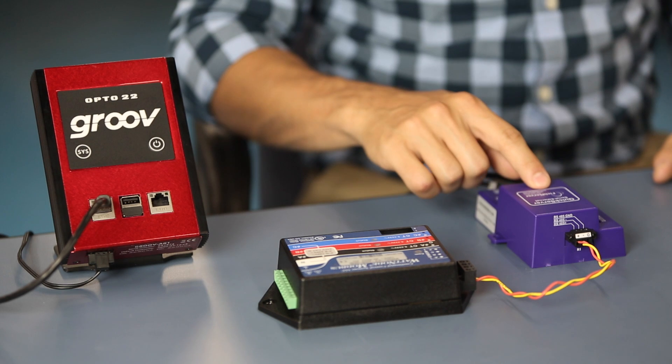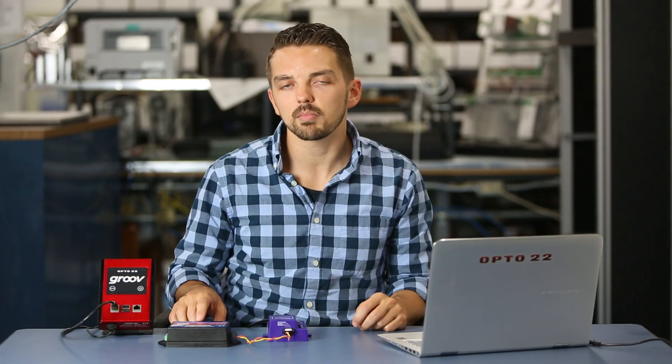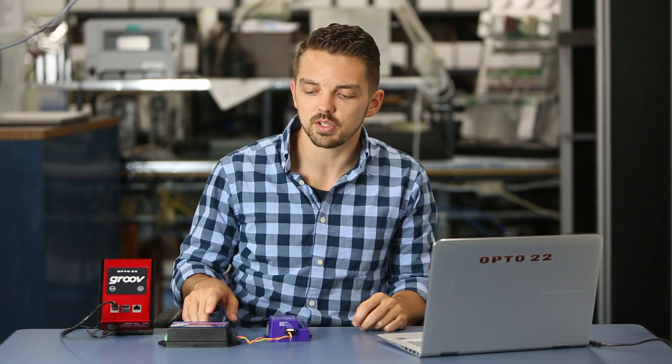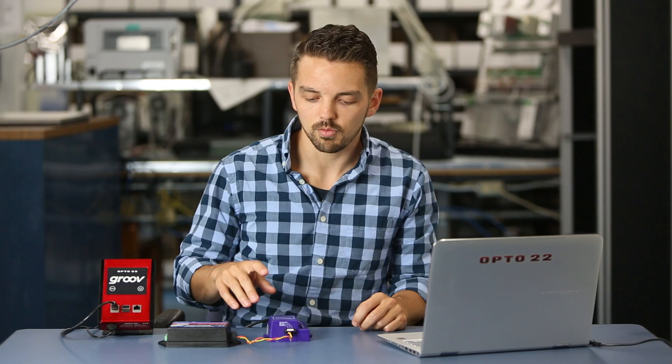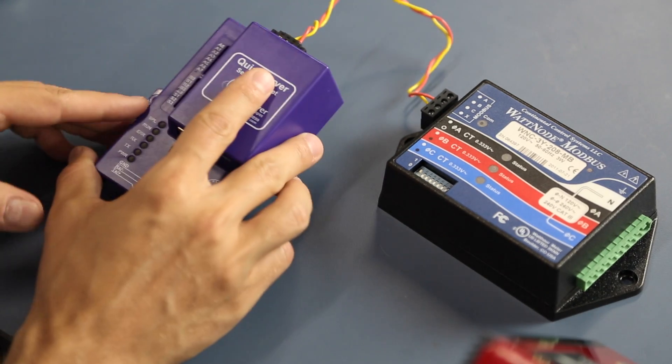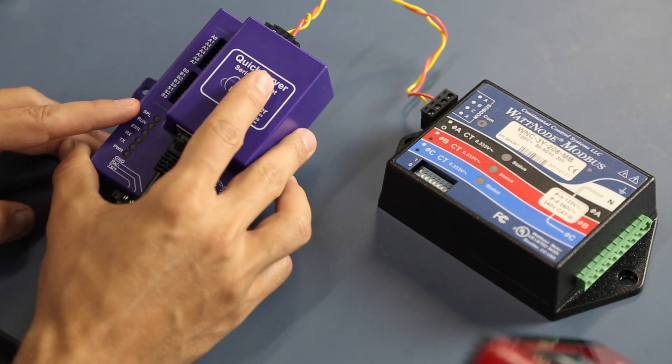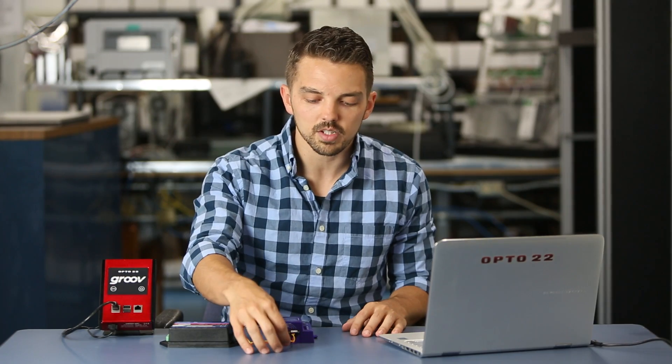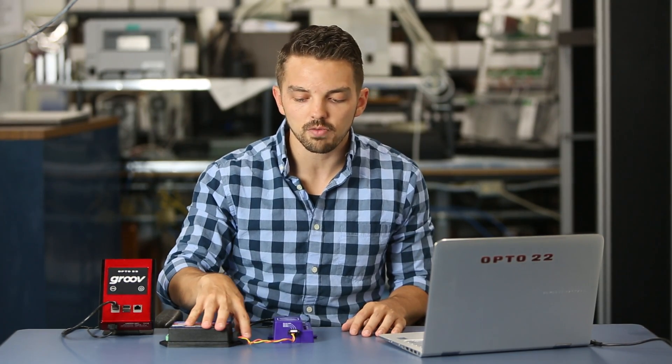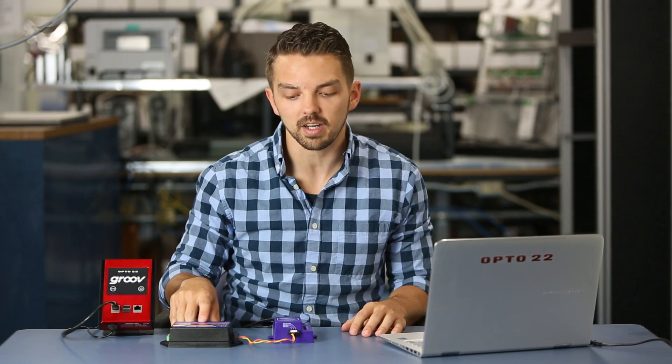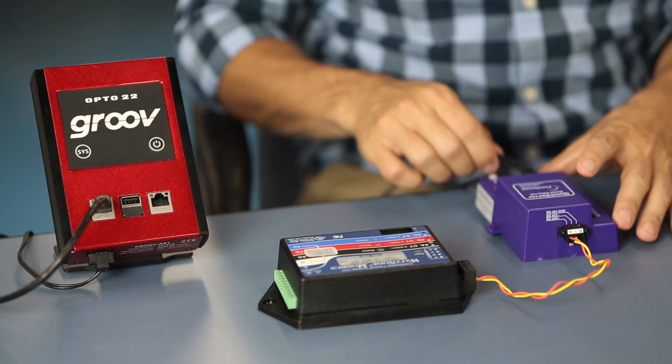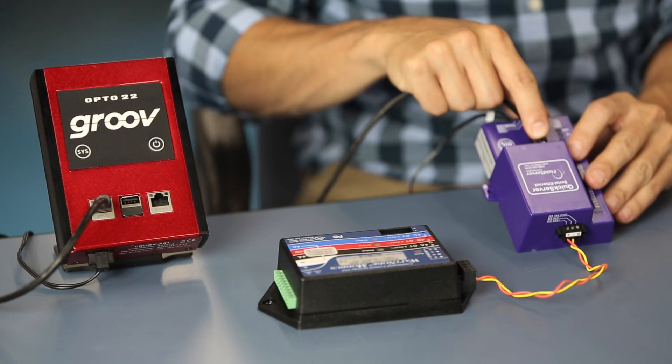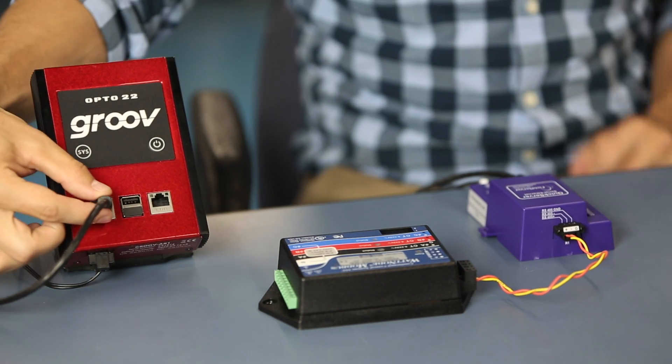I'll be using the quick server by field server to connect the Modbus RTU device directly into Groove. The quick server is especially useful for Modbus RTU to Modbus TCP because of PEX mode, which is also called Port Expander mode. On the quick server, we'll be using all of the default DIP switch settings. You can see here that it's wired with two wires for our RS-485 signal to our Modbus RTU device, and wired here into our Modbus TCP network, as well as our Groove being on the same network.